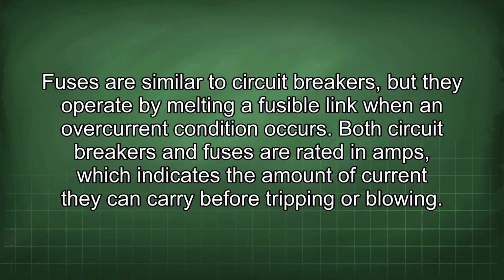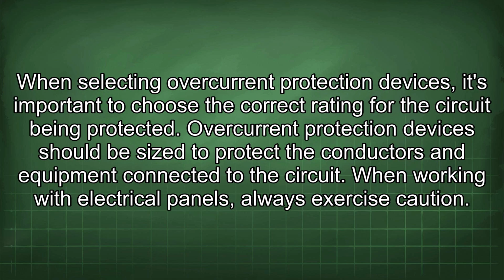Fuses are similar to circuit breakers, but they operate by melting a fusible link when an overcurrent condition occurs. Both circuit breakers and fuses are rated in amps, which indicates the amount of current they can carry before tripping or blowing. When selecting overcurrent protection devices, it's important to choose the correct rating for the circuit being protected. Overcurrent protection devices should be sized to protect the conductors and equipment connected to the circuit.